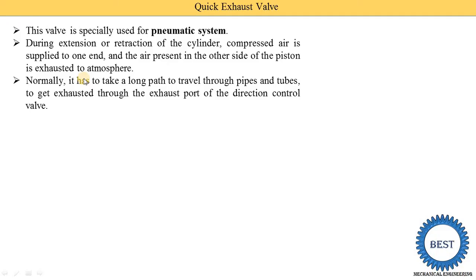The directional control valves are connected with the actuators — one port is connected to the cap end port and another to the rod end port. During extension, compressed air is supplied to the cap end side and air is exhausted from the rod end side back through the directional control valve to the atmosphere. In a hydraulic system the oil coming back from the rod side is supplied to the tank and reused, but in a pneumatic system the exhaust air must be released to the atmosphere.